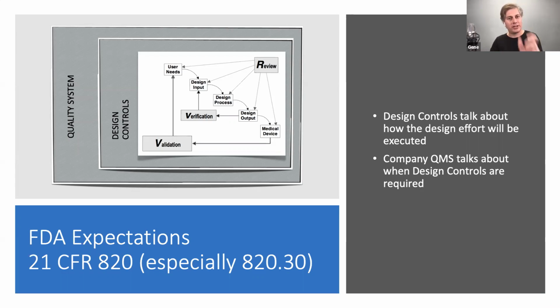Do you see where this difference between a checklist and a process comes in? If you're thinking, I've just got to go out and test these things and send it to FDA and I'm going to get my 510K, the reality is they're expecting those checklist items to emerge from a process that looks like what's on your screen in front of you. It is easier to implement design controls for a face mask than it is for a heart-lung machine. There's a lot more to do when you have a more invasive device that may be life-sustaining or things like that. But nevertheless, that process is part of the expectation. It's what the FDA is expecting.